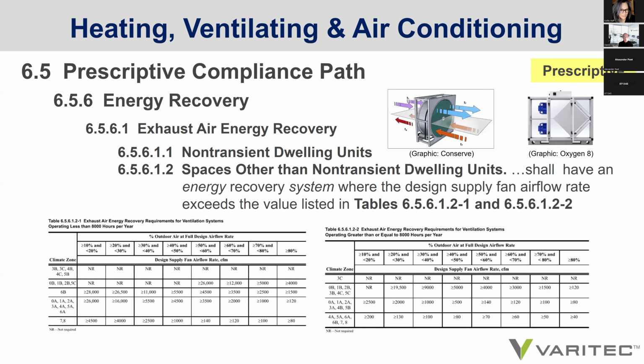There is new prescriptive language on energy recovery units. Spaces other than non-transient dwelling units shall have an energy recovery system where the design supply fan airflow rate exceeds the value shown in tables 6.5.6.1.2-1 and 6.5.6.1.2-2. So you would have to pay attention to those to see whether or not an HVAC design would fall under the requirement to provide energy recovery.